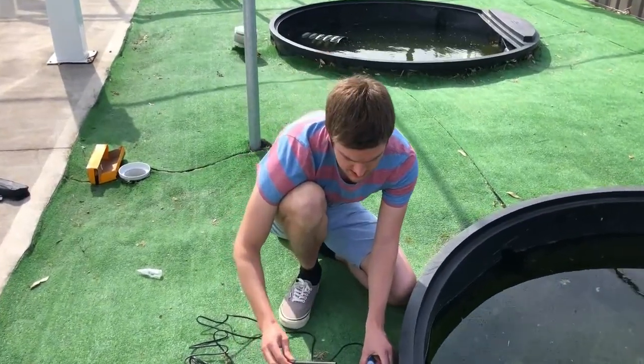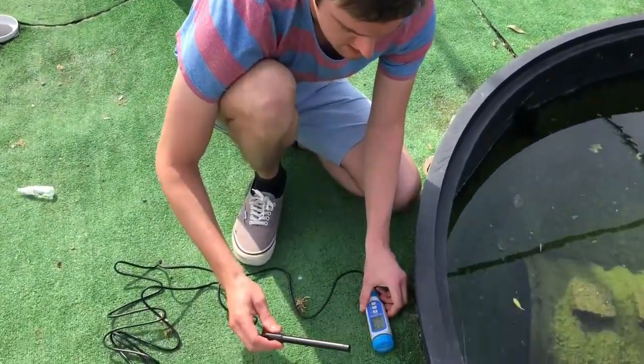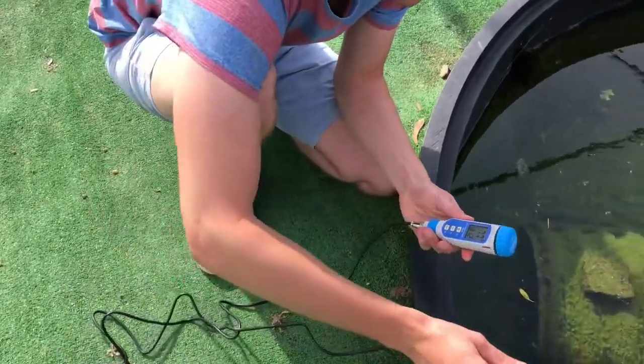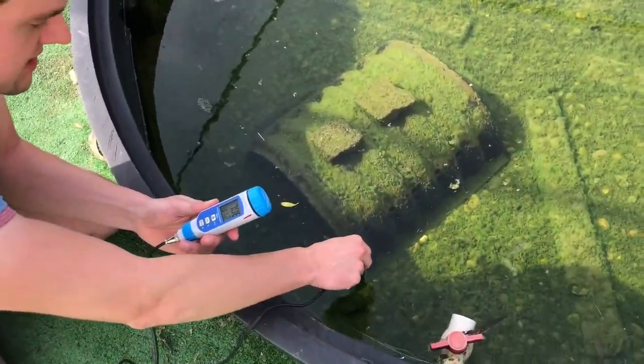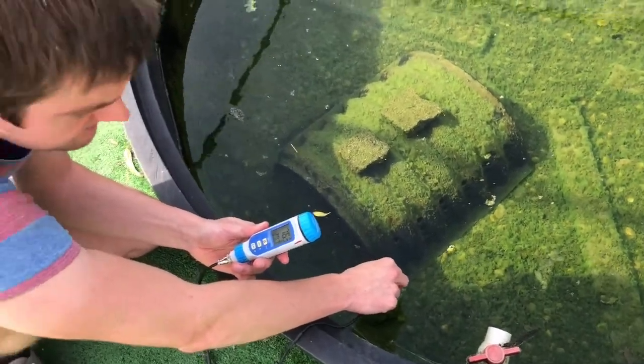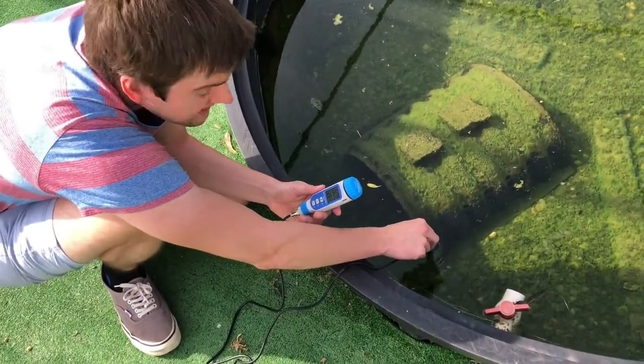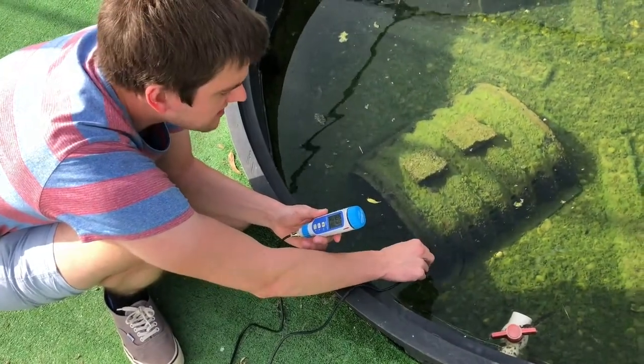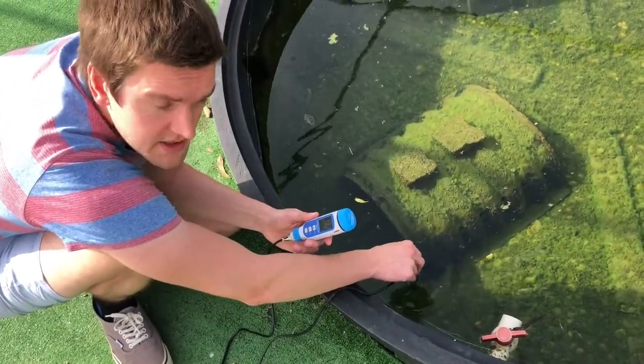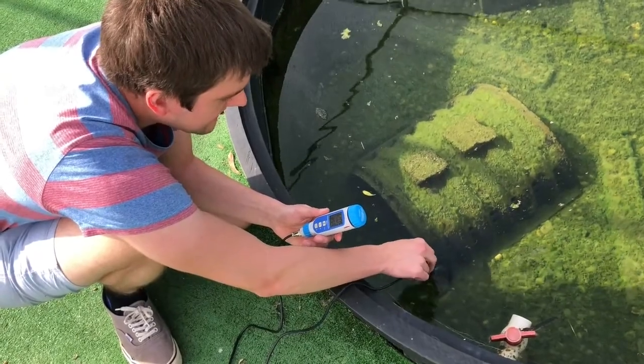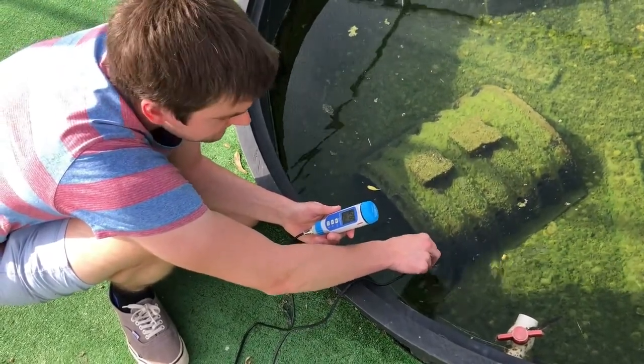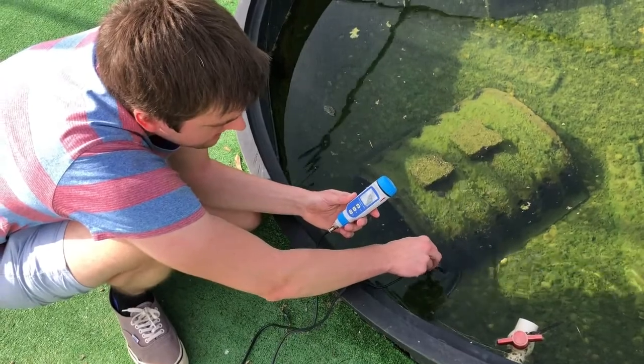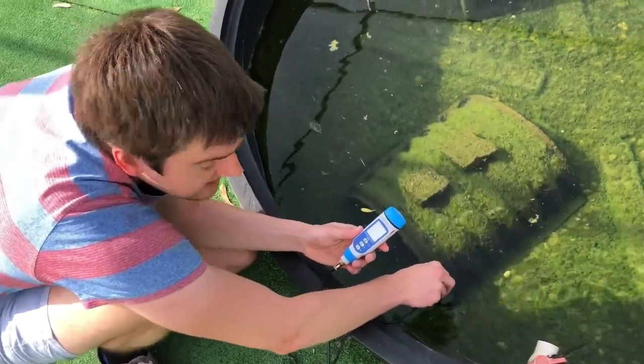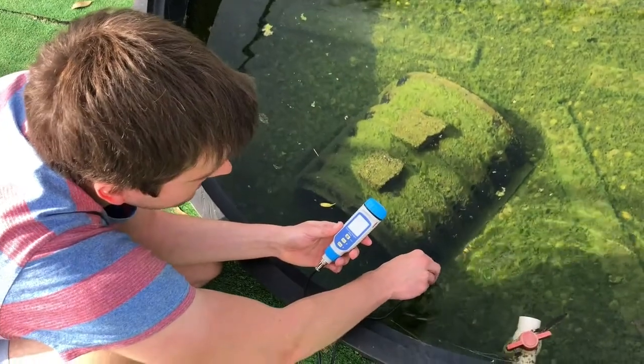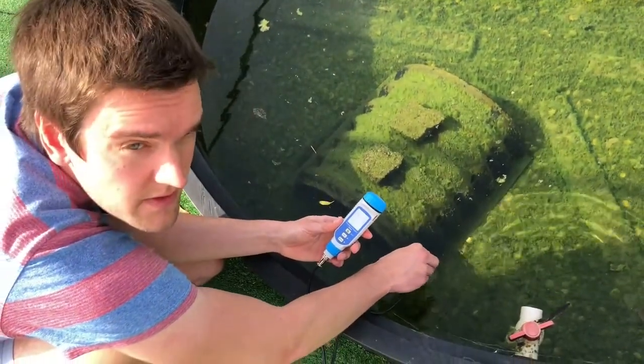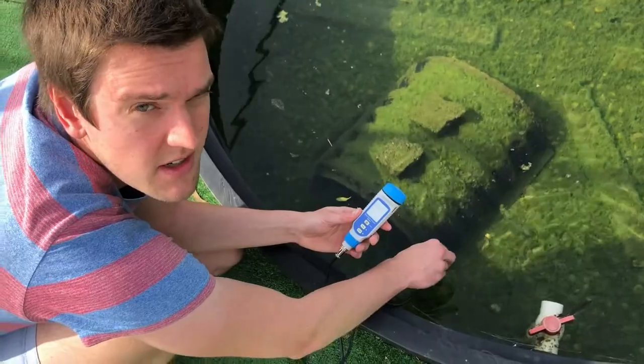Okay, now we're going to show how to use the probe. So what we do is we put the probe into the water so the probe head's immersed, and the way this probe works is that you need to constantly be moving it around so it's got access to flowing water. And looking at your meter, approximately after about 30 seconds, it should give you an accurate reading of dissolved oxygen and temperature.